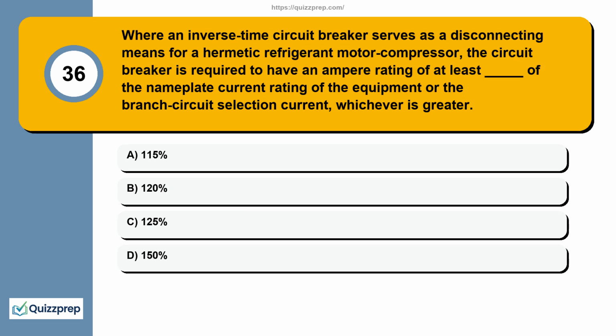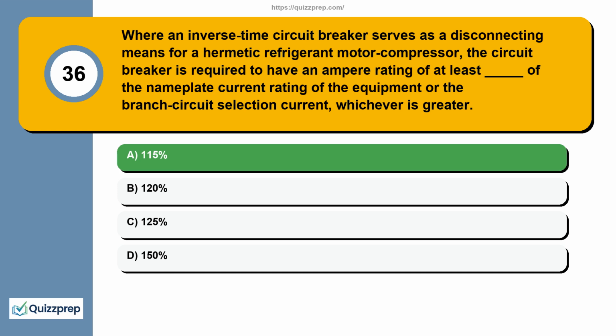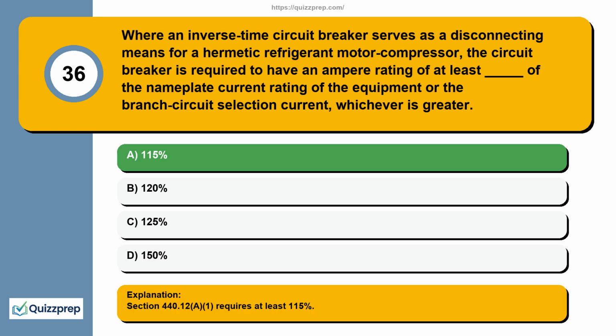Question 36. Where an inverse time circuit breaker serves as a disconnecting means for a hermetic refrigerant motor compressor, the circuit breaker is required to have an ampere rating of at least what percent of the nameplate current rating of the equipment or the branch circuit selection current, whichever is greater? 115%, 120%, 125%, 150%. Section 440.12(A)(1) requires at least 115%.